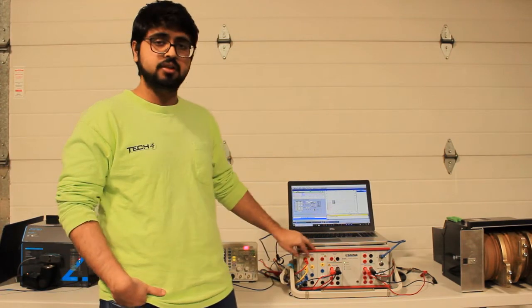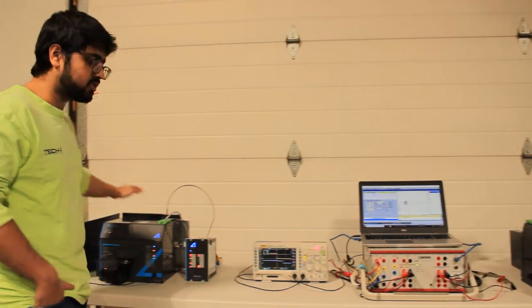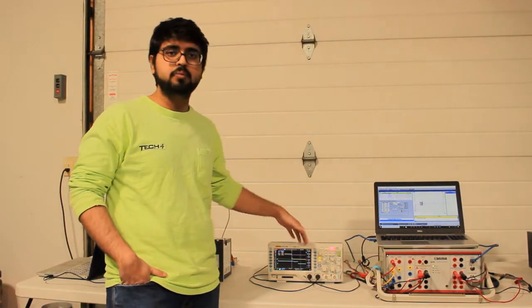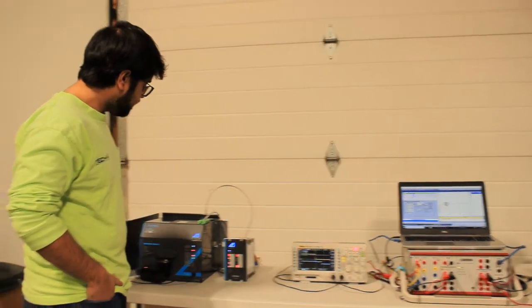That's not the exact time the quencher takes to quench. That is why we've used an oscilloscope to verify that it quenches under five milliseconds. One other thing about the Arteche AQ-1000 device itself: it's the only resettable arc quencher device in the market.